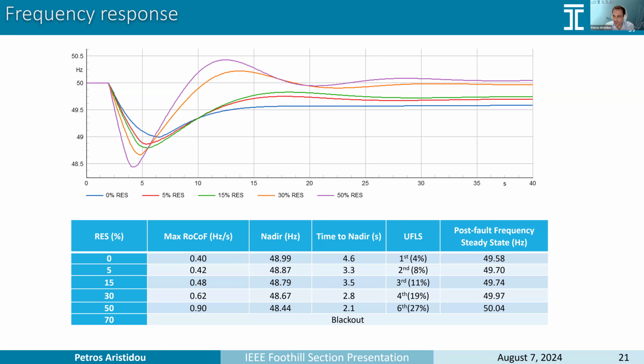How do you actually control them? If you want to send set points and everything, it becomes very, very difficult. So they prefer to have centralized solutions like grid forming batteries or synchronous condensers or things like that, that they can actually dispatch and control rather than rely on these hundreds of thousands of small units. But again, that's a preference of the Cyprus TSO. Okay, thank you.